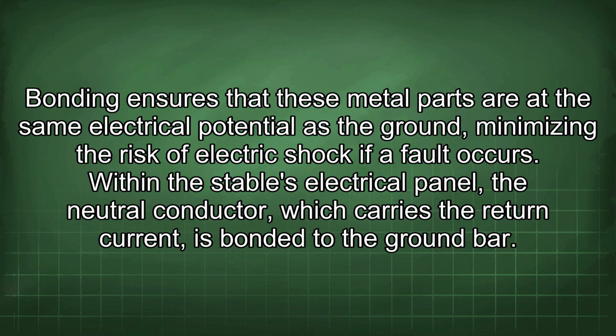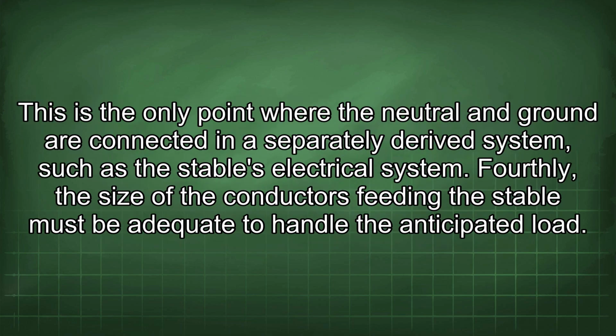Within the stable's electrical panel, the neutral conductor, which carries the return current, is bonded to the ground bar. This is the only point where the neutral and ground are connected in a separately derived system, such as the stable's electrical system. Fourthly, the size of the conductors feeding the stable must be adequate to handle the anticipated load.